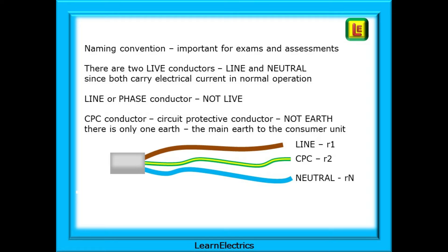We also have the CPC conductor — the circuit protective conductor. The conductor in the cable should not be called the earth, as there is only one earth in the property: the main earth to the consumer unit. The line can also be called little r1, the CPC is little r2, and the neutral can be called little rn.